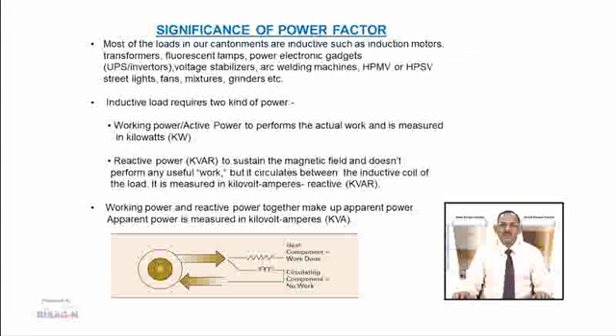Inductive loads require two kinds of power. First is working power or active power, which performs the actual work and is measured in kW. Second is reactive power in kVAR, which sustains the magnetic field and does not perform any useful work but circulates between the inductive coil of the load. Working power and reactive power together make up apparent power, measured in kVA.